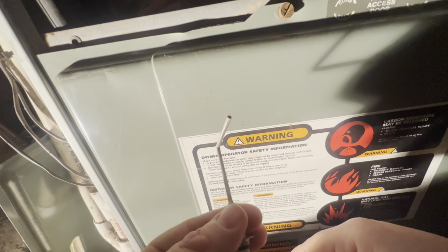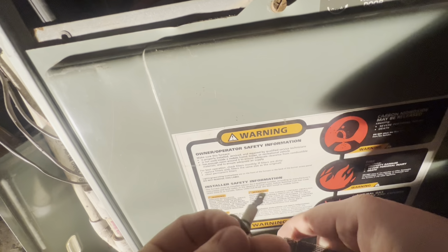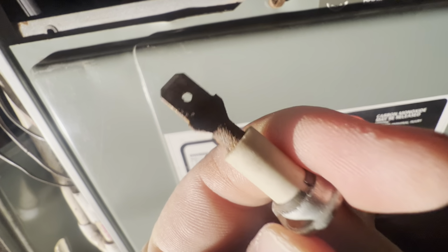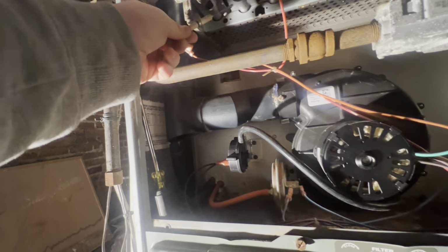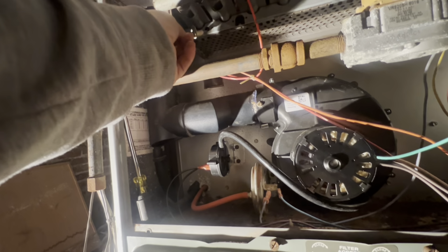That's why it's really important to make sure that your furnace has a ground, a proper ground. If your connections are getting pretty rusty like this one right here, you want to clean that up too. But make sure you got good contact, guys. You don't want any kind of resistance. Rust equals resistance. So we'll get this guy cleaned up, get them installed back in the unit. So it's actually very simple to install this. All you have to do is put it right up in the hole, just like that.